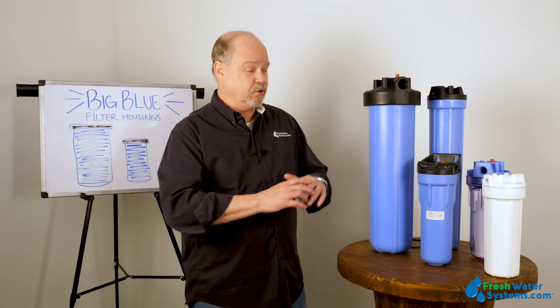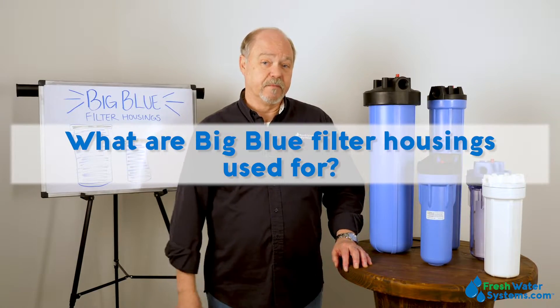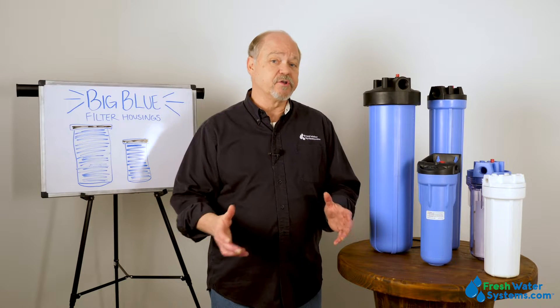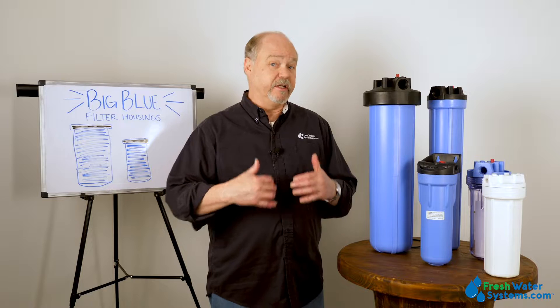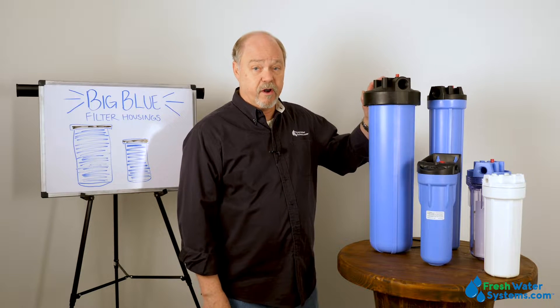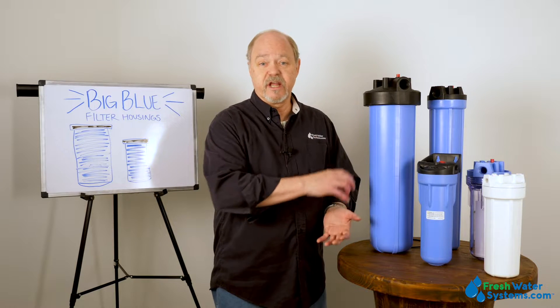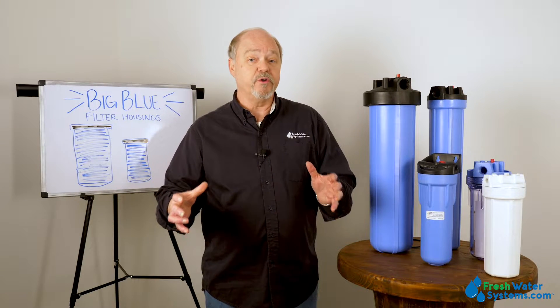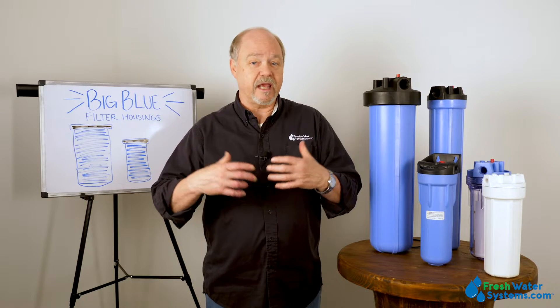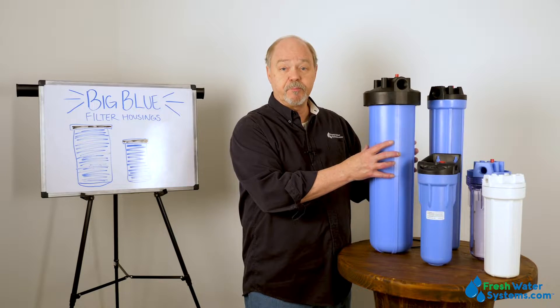It's literally a filter housing, and you could put a variety of cartridges inside depending upon what you're trying to filter. These housings are used for point of entry filtration, typically residentially, but they can also be used commercially — any place we've got to have a little bit more flow rate than a regular standard sized filter housing will accommodate. Whether you put a sediment filter in it, some type of a carbon filter, or a specialty type filter that might have ion exchange resin or some type of media that's catching arsenic, for example, these housings are probably the most widely used pieces in the water treatment industry.